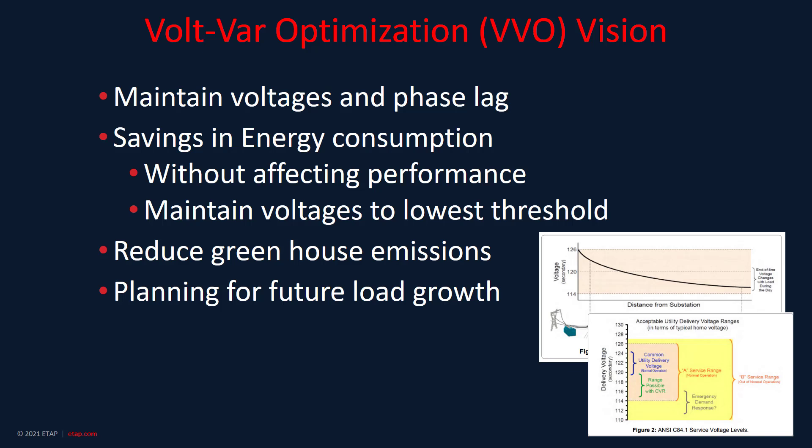The principle of CVR is that savings in energy consumption are achieved by reduction of voltage level without affecting the performance of the customer's devices, demand, and minimizing system losses. This means that total power demand can be reduced by operating in the lower allowable range of the voltage, as shown in figure number two.